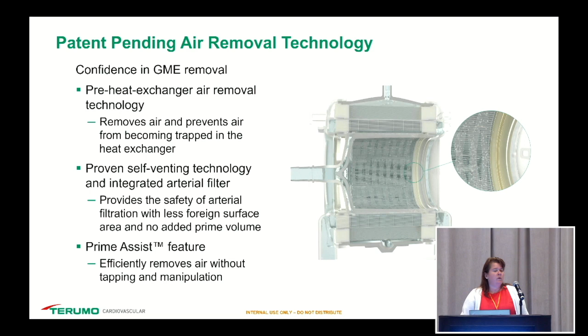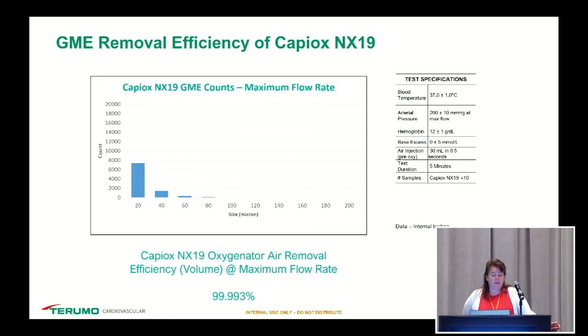So the GME removal efficiency was a test that we did in the lab. The test specifications are off to the side there, but essentially they took 30 mLs and injected it into the oxygenator in 0.5 seconds. Over 5 minutes, they did 10 samples, and they were able to show that the GME had maximum counts of 20, so that makes sense, right? Because there's a 32 micron filter within the oxygenator itself. And we also know that from 10 to 40 microns, the GME is considered small, and in some research papers it's considered noise and not necessarily significant. So as you can see, the GME counts at the flow rate of 8 liters are very small.